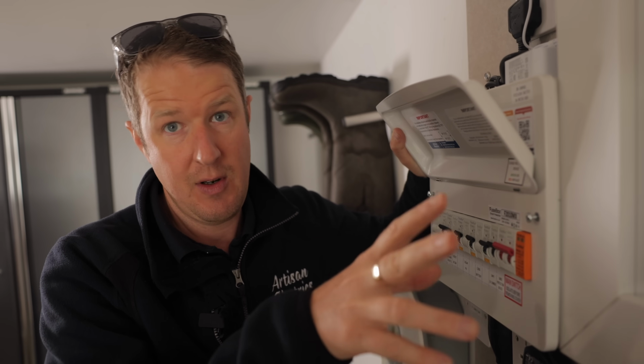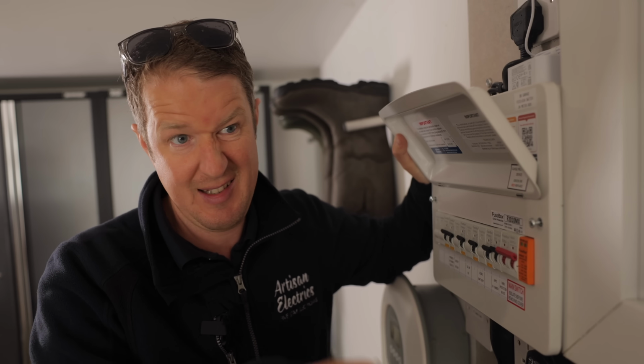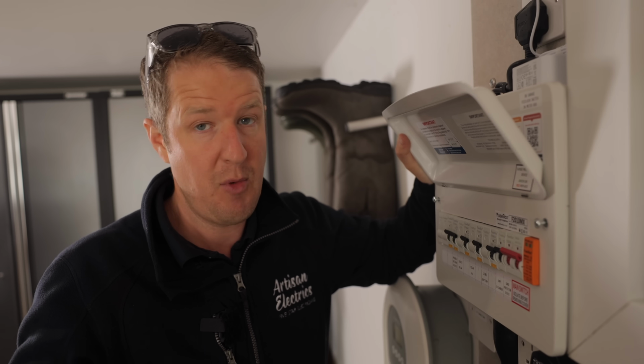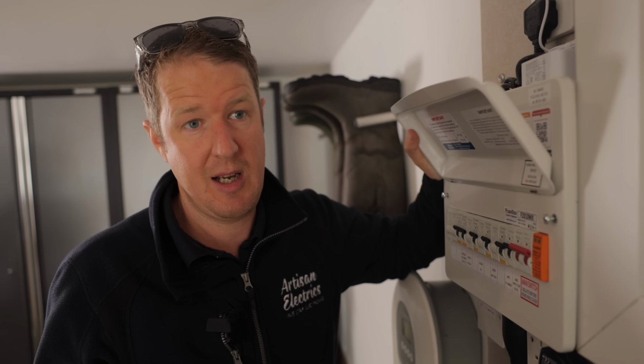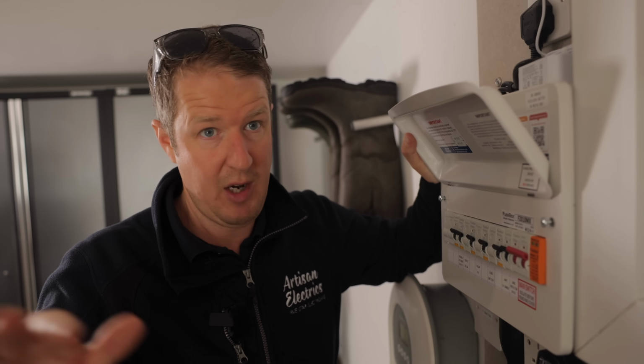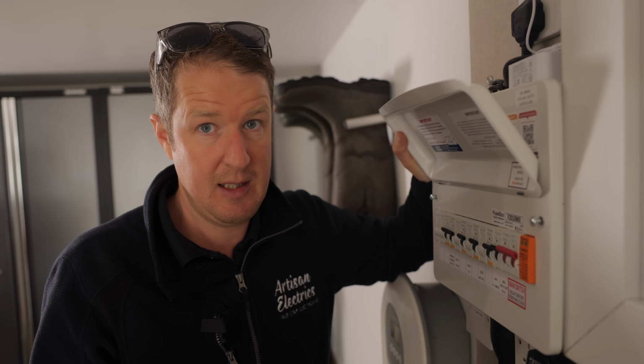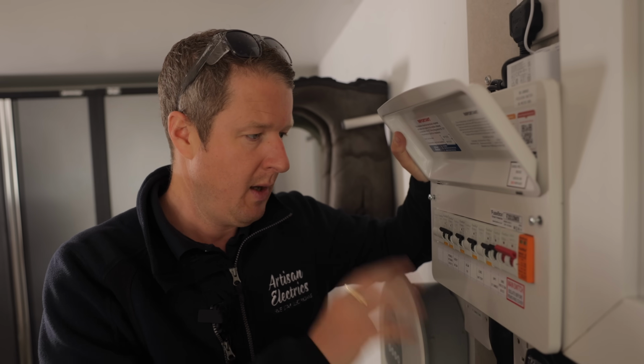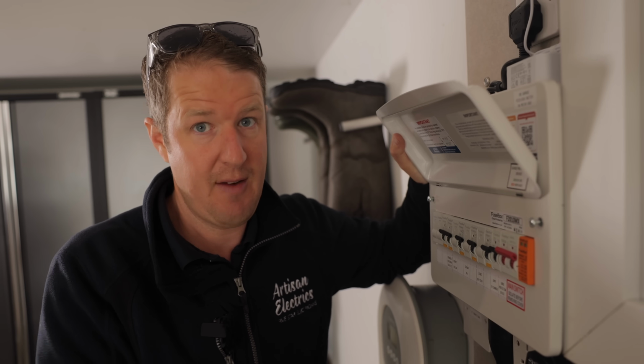The fact is the SolarEdge inverter doesn't need RCD protection unless the cable supplying it does. Same with the Libbi inverter - it doesn't need RCD protection if the cable is run in trunking or similar. So we're going to put them on MCBs instead of RCBOs.